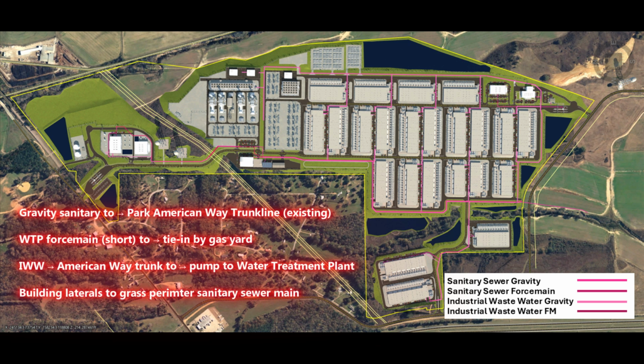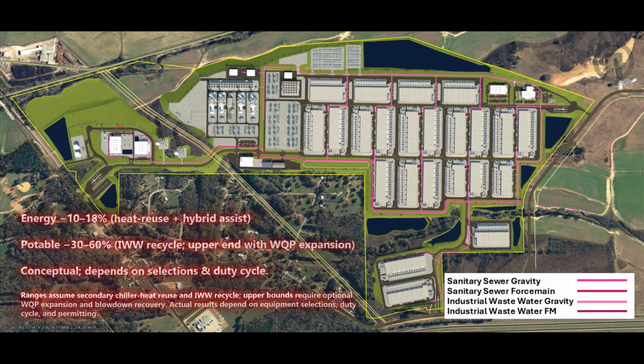Industrial/process water is treated on-site at the water quality plant and reused for cooling and non-potable needs. Only permitted surplus, if any, leaves the loop. Final routing set in detailed design. Industrial/process water is polished at the on-site water quality plant and recirculated for tower makeup and non-potable uses. With optional water quality plant expansion and blowdown recovery, the campus could cut cooling energy approximately 10 to 18% and potable makeup approximately 30 to 60% versus a conventional plant.